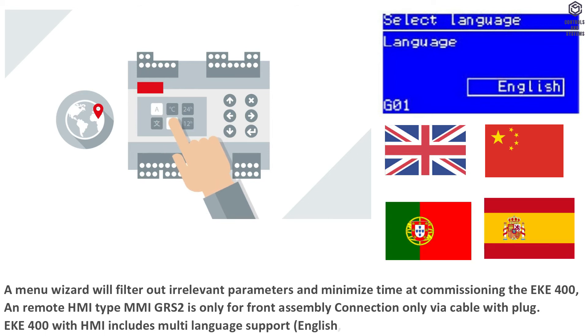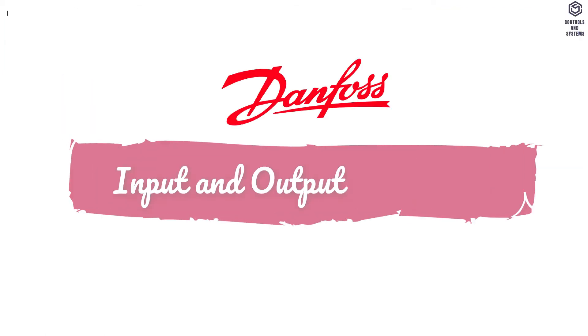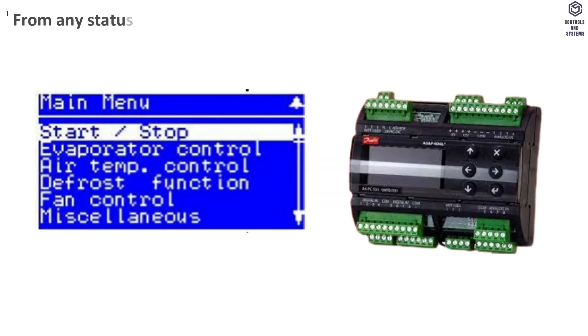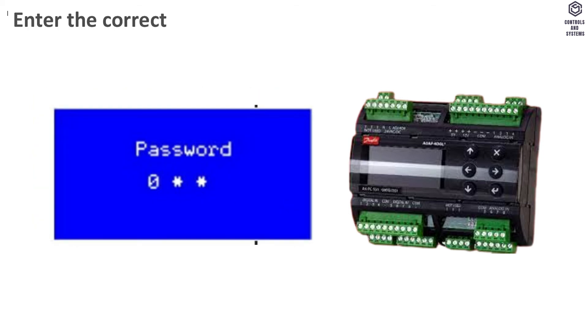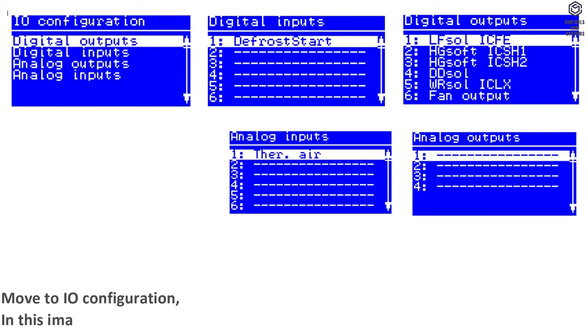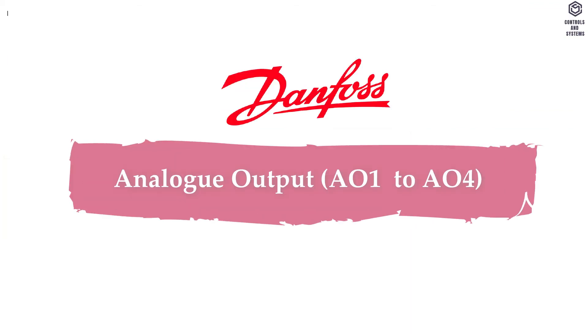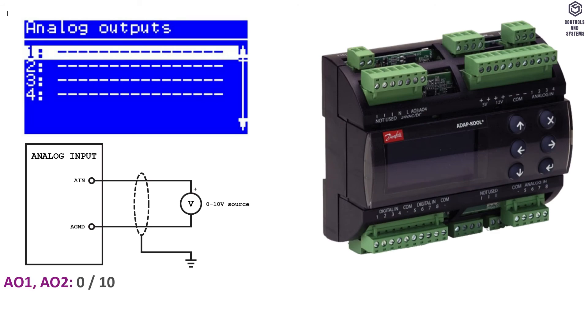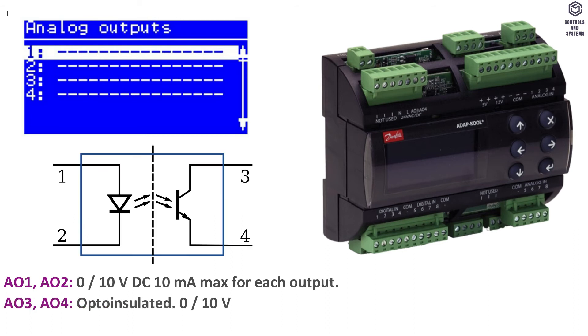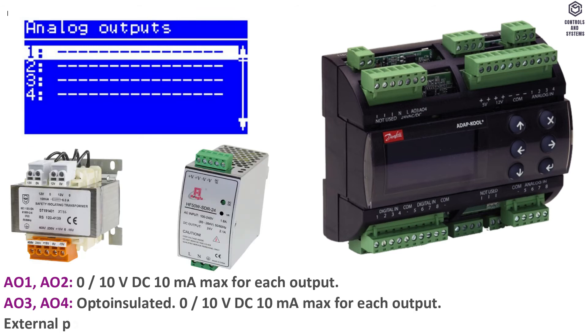The EKE400 with HMI includes multi-language support. For input and output navigation, from any status screen press Enter for 2 seconds to access the main menu, enter the correct password, and move to I/O configuration to see how many outputs and inputs your settings have provided. Analog outputs AO1 and AO2: 0 to 10V DC, 10mA maximum for each output. AO3 and AO4: opto-isolated, 0 to 10V DC, 10mA maximum for each output — note: external power supply 24V AC or 24V DC required.